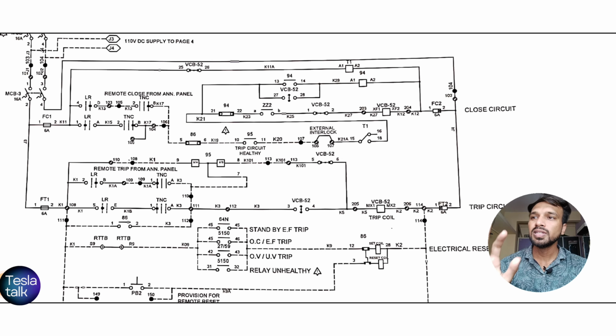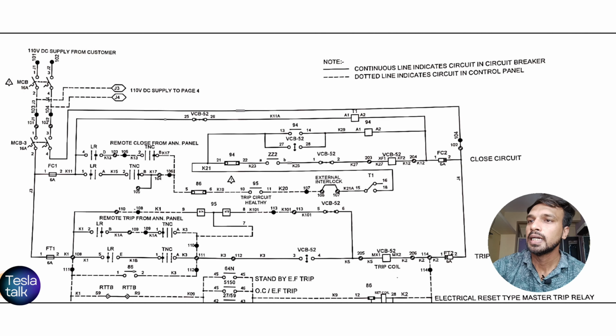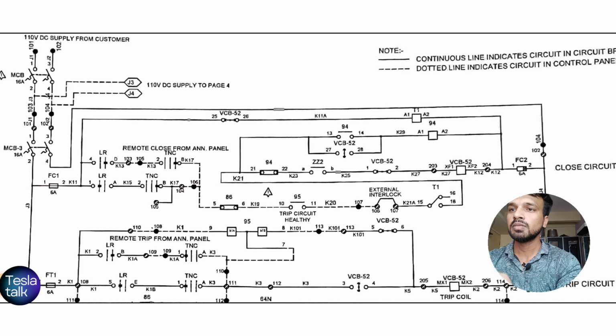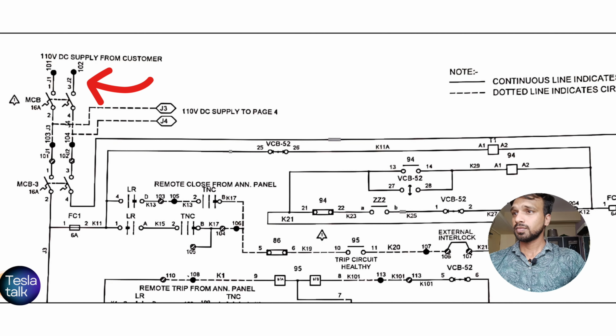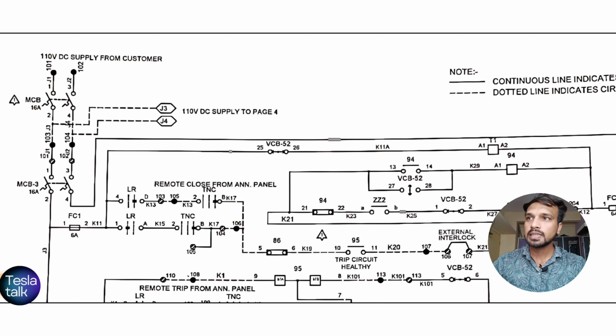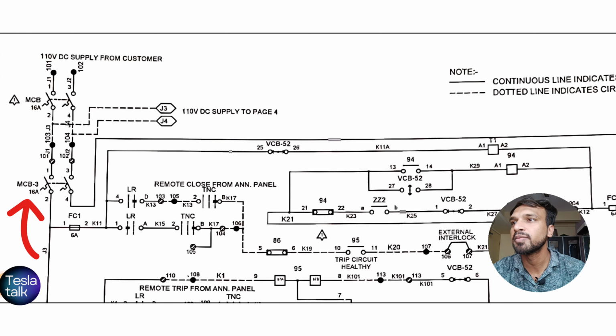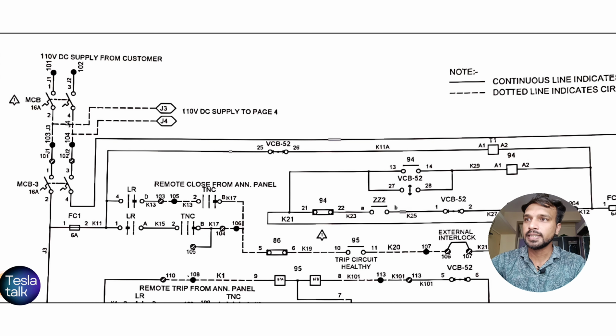So we will focus on how this circuit ensures the safe operation and protects the system during faults. We will see first the power supply. This is the 110 volt DC power supply coming from the customer, and the power for this system comes from a 110 volt DC supply, which is connected via terminals labeled J3 and J4. You can see here J3 and J4 are the terminals, and there is a miniature circuit breaker, a 16 ampere MCB, which is used to ensure safety. Then this supply powers both the control and trip circuits.